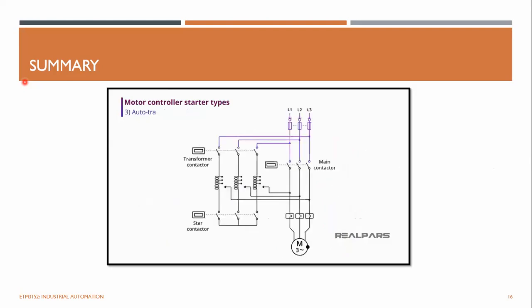Auto transformer motor starters are commonly used in reduced voltage starting applications, especially with large motors. When the motor starts, two contactors pull in. One of these contactors energizes a transformer circuit, and the other forces the transformer into a star configuration. The tapped output from the transformer is connected to the motor leads at the start. Once the motor reaches 85 to 90% of full voltage, the star contactor opens, and the transformer then acts as a choke to limit the voltage and the current to the motor. The main contactor then closes, and the motor controller acts as an FVNR with full voltage to the motor.